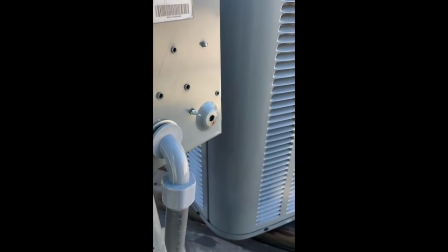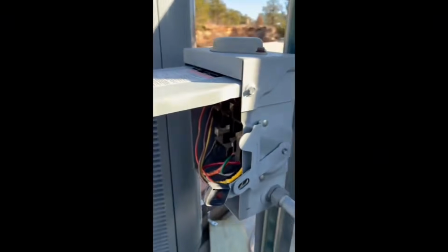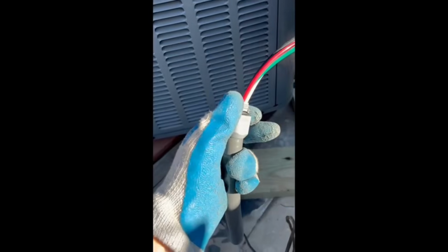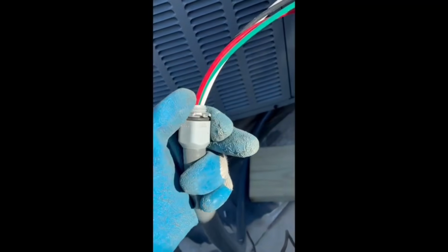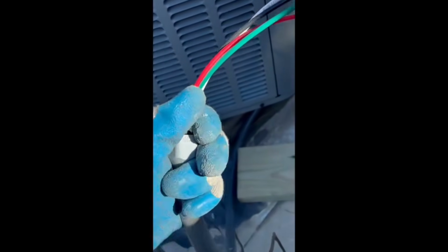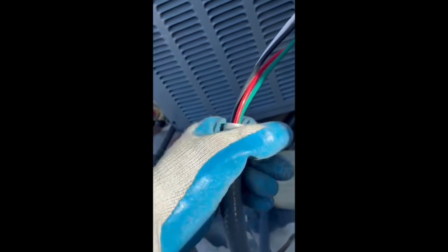Again, just unistrut. And some rain tight or liquid tight connectors and flexible conduit. We've got our 3 hots and our green ground. And these connectors, you just tighten them down like so. Pretty easy to use. And remember, being 3-phase, you want to be careful when you first turn on the condensing unit that your compressor is spinning in the proper direction and that your condenser cooling fan is spinning in the proper direction.